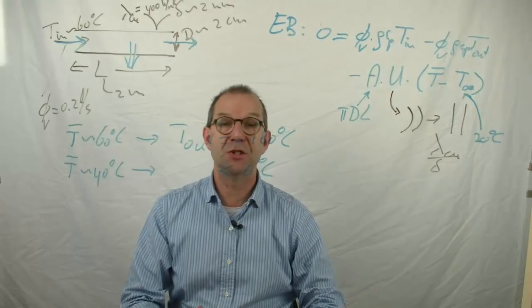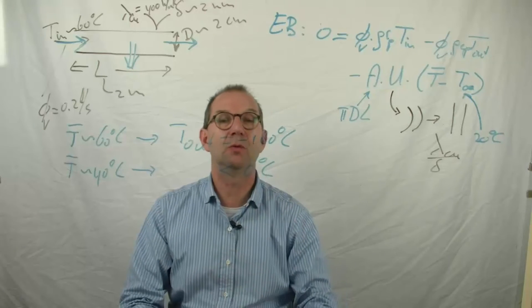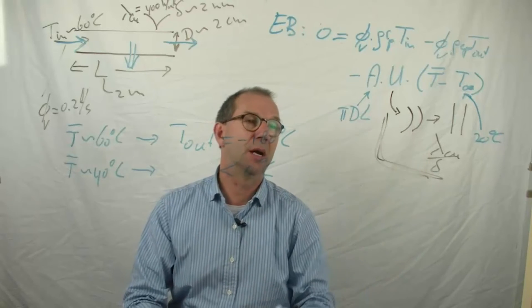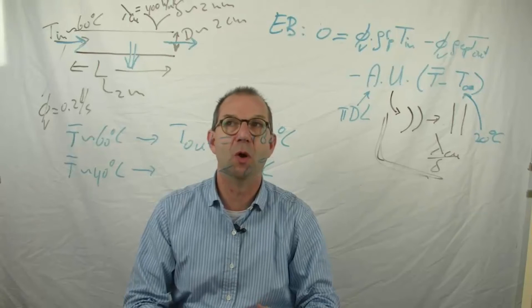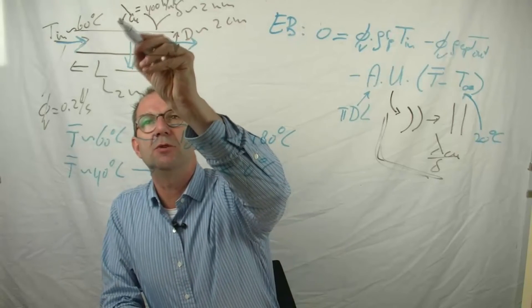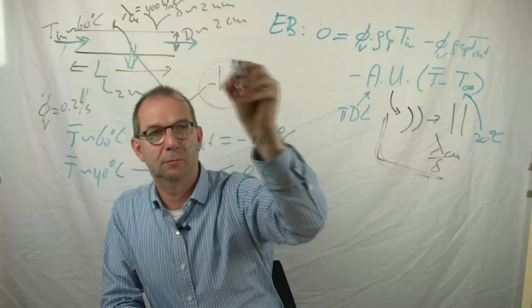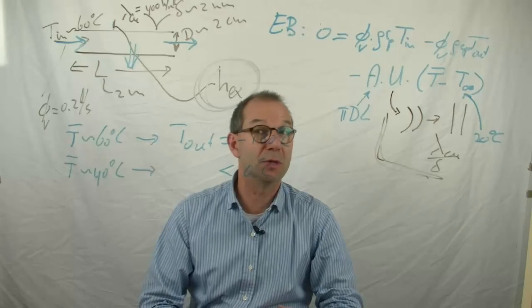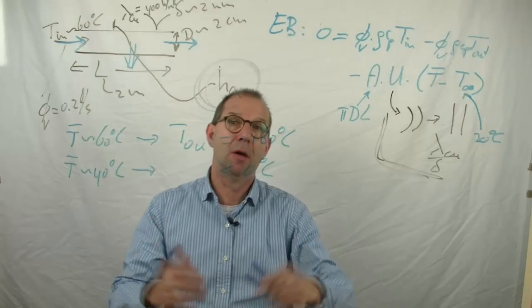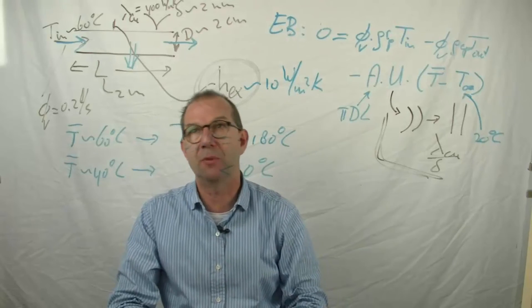If this is the picture, you better insulate the tube, because all heat is gone in the first two meters — you never warm up the rest of the house. But before I start insulating I need to rethink this. The other assumption is that the total heat loss is governed only by the conductivity of the tube wall, and that may not be the case. This is a very good conductor, but you also need to get the heat out into the surroundings — into the air. Air is a bad conductor. What if there is an external heat transfer coefficient of the order of 10 watts per meter squared Kelvin — a typical value in practice for these systems?